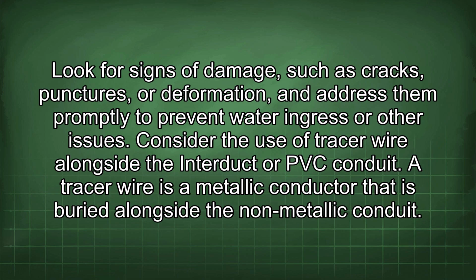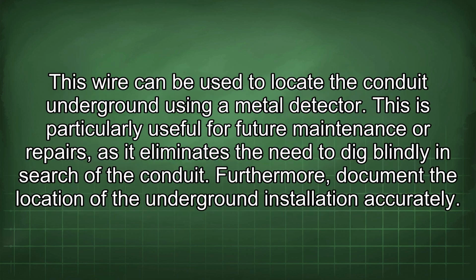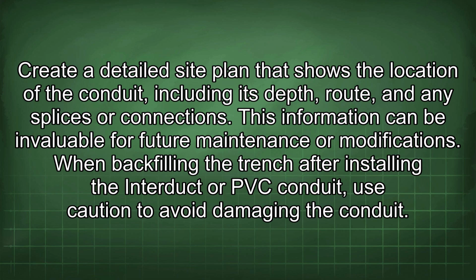A tracer wire is a metallic conductor that is buried alongside the non-metallic conduit. This wire can be used to locate the conduit underground using a metal detector. This is particularly useful for future maintenance or repairs, as it eliminates the need to dig blindly in search of the conduit. Furthermore, document the location of the underground installation accurately. Create a detailed site plan that shows the location of the conduit, including its depth, route, and any splices or connections. This information can be invaluable for future maintenance or modifications.